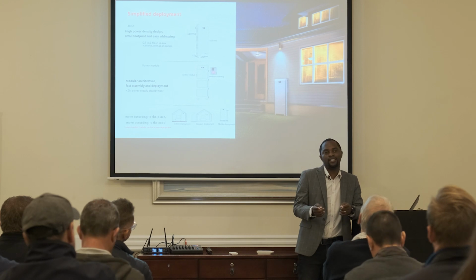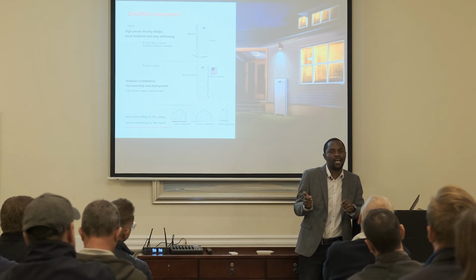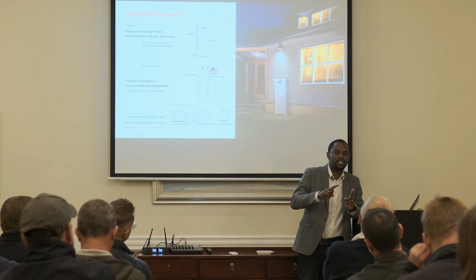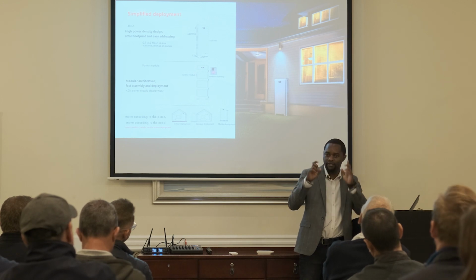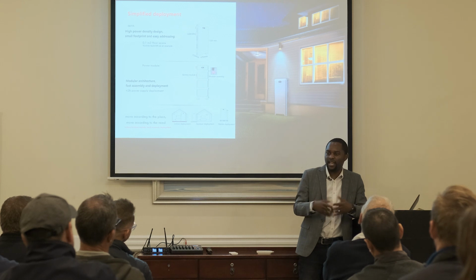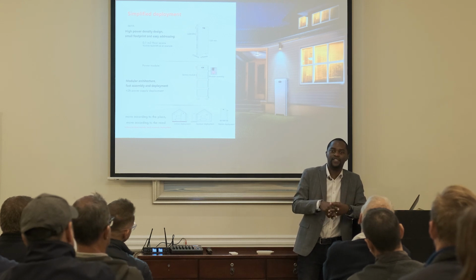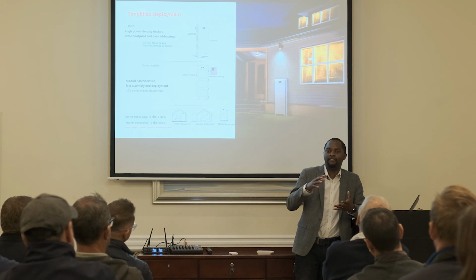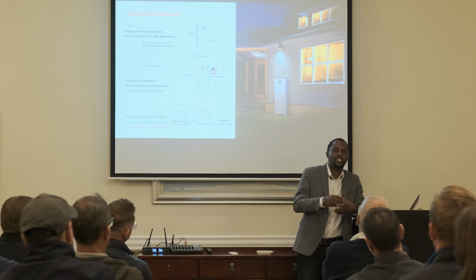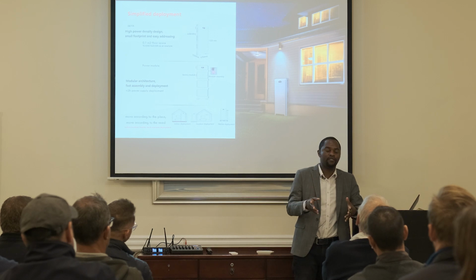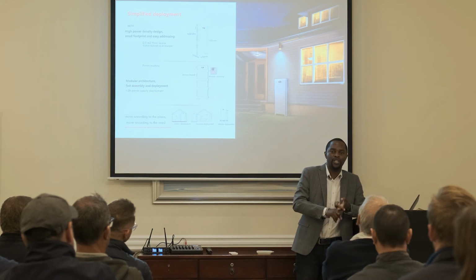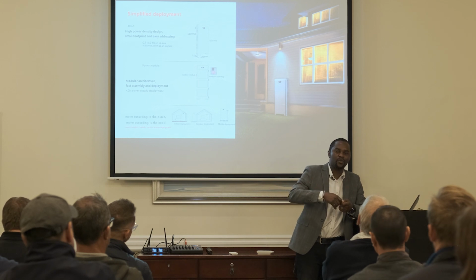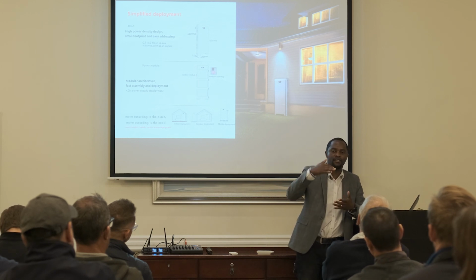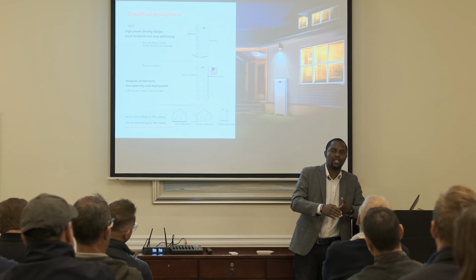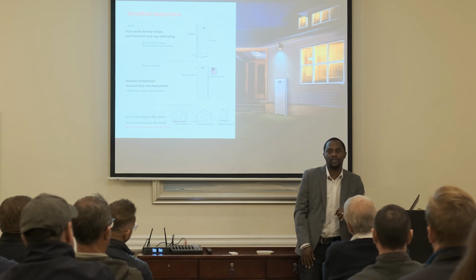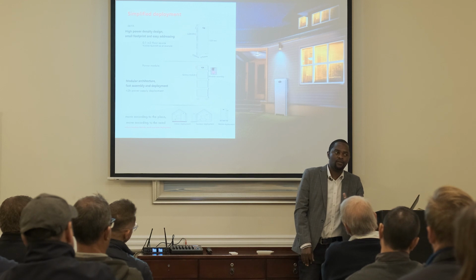But remember now, the earth leakage trips not so much for the voltage, but for the current. That's why the tests have determined that you need to have 0 ideally, but it can't be 0. I mean, 5 volts, 6 volts is good enough. If it's less than 20 volts, you can actually have your inverter working in that scenario without tripping. If it gets more than 20 volts, that's when you now need to bond. When you are bonding neutral to earth, you are shorting it to earth, so whatever voltage is there goes to ground. It's now at ground level and becomes ideally close to 0. So 0 is the ideal, but you might not get 0.